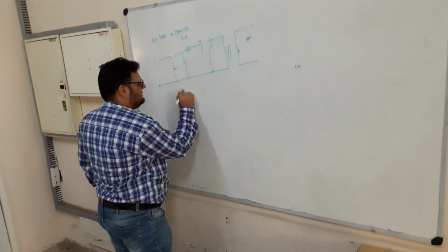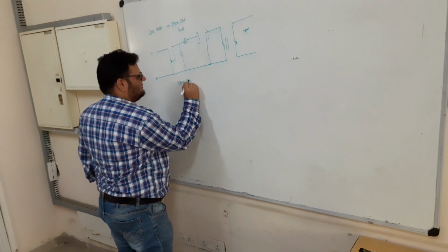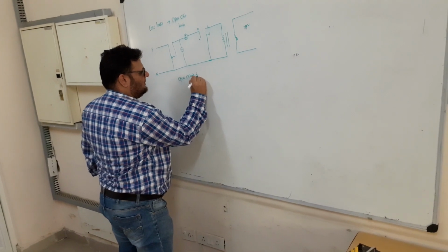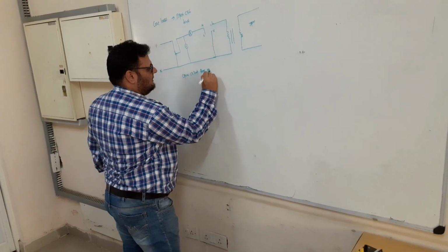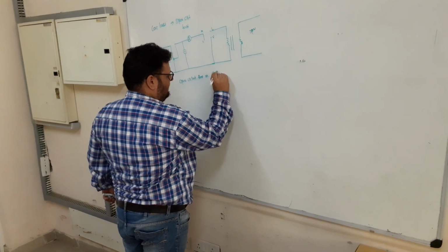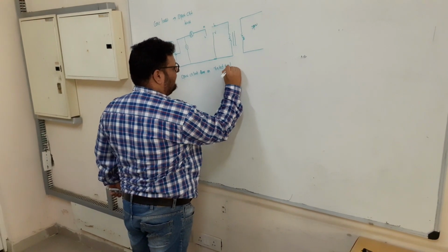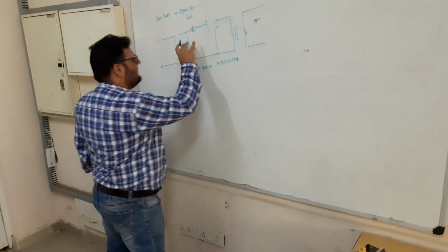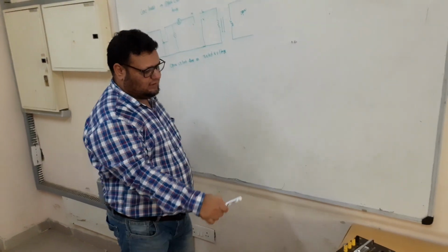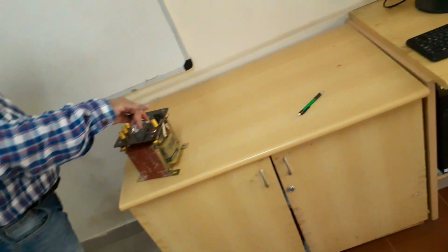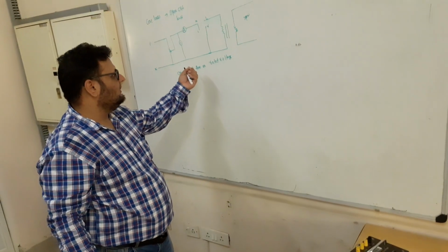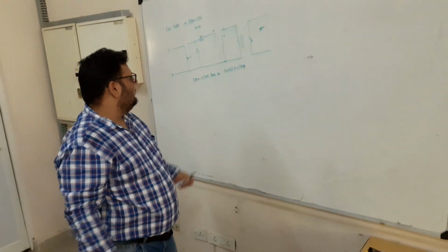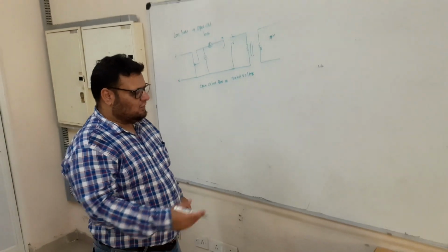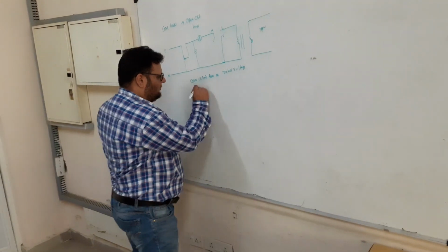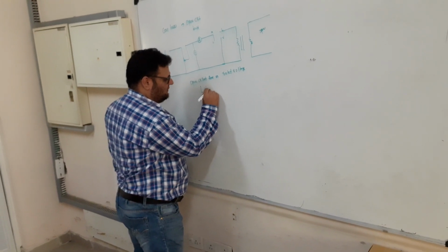Open circuit test would be done on rated voltage. So you want rated voltage. That is the reason I have connected a variac, because I want rated voltage. Suppose over here it is showing 230 volts. So in the primary winding, in the LV side, I want this 230 volts. Then only my open circuit test would be carried out. So usually an open circuit test is carried out on the LV winding, the low voltage winding.